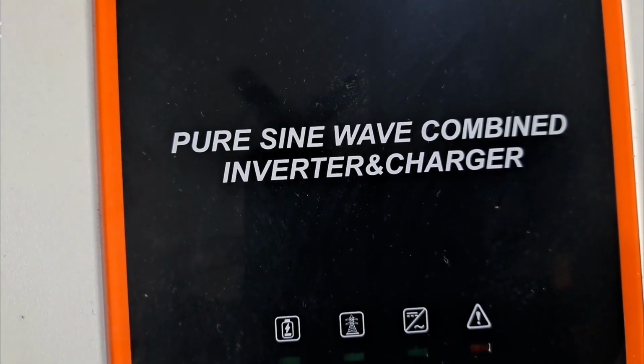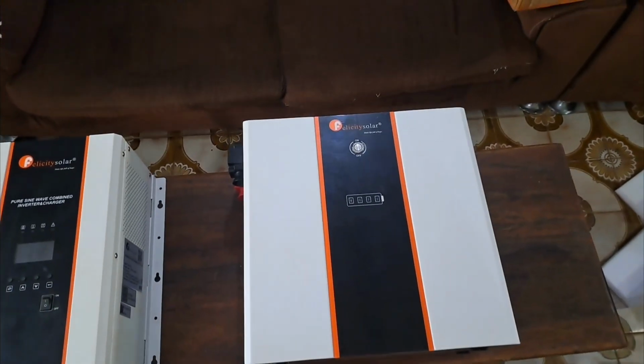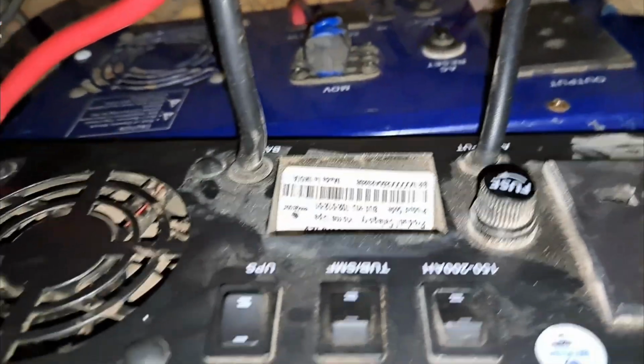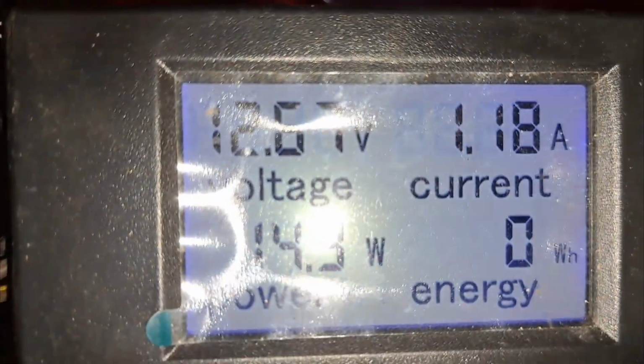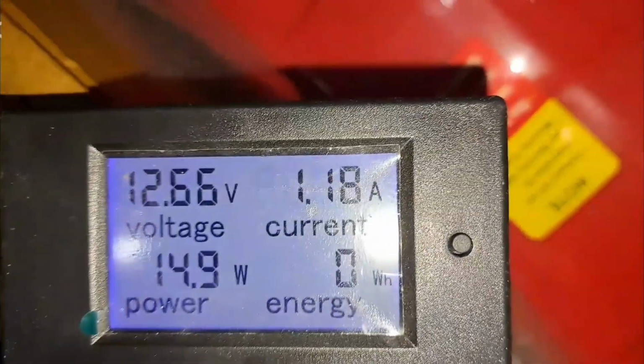I've been doing a capacity test for different inverters, and the results show that you have to size your inverter correctly. Here's one of the tests I carried out: this is a 1 kVA inverter, and nothing is connected to the back of it. Just turning it on, it's pulling 14 watts from my system.